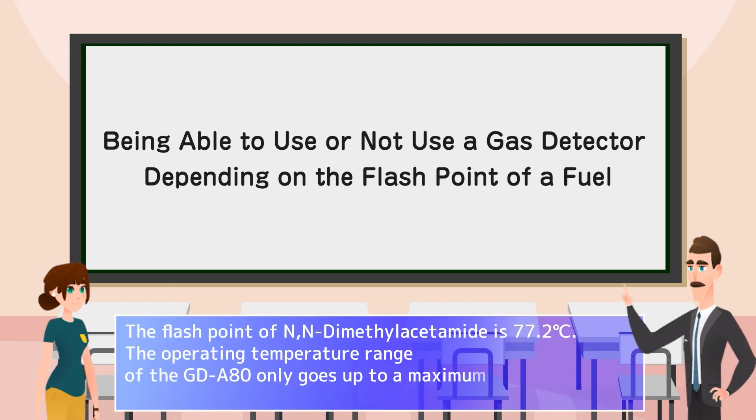The flash point of N,N-dimethylacetamide is 77.2 degrees Celsius. The operating temperature range of the GDA80 only goes up to a maximum of 53 degrees Celsius, so you won't be able to monitor it at 100% LEL.